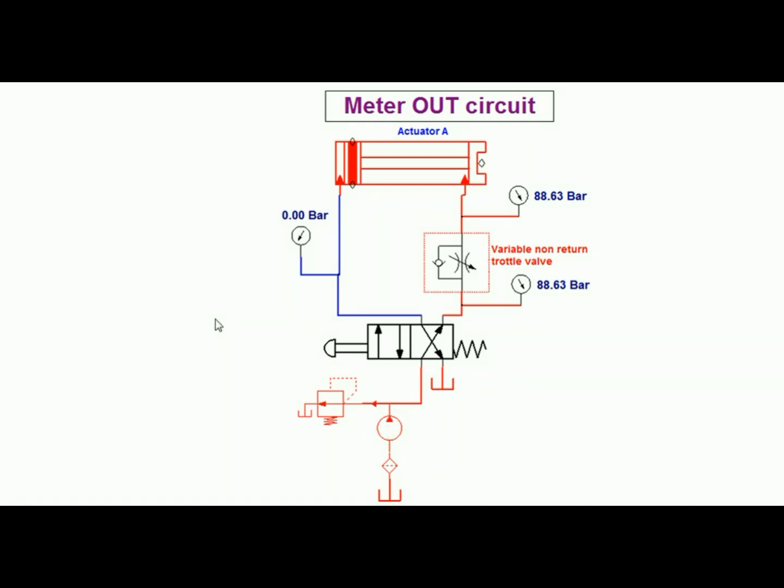Pressure intensification occurs on the rod side when the meter out operation is carried out without a load on the rod side of the cylinder and can result in failure of the rod seals.